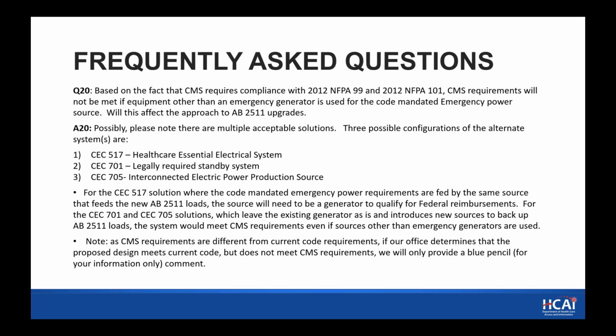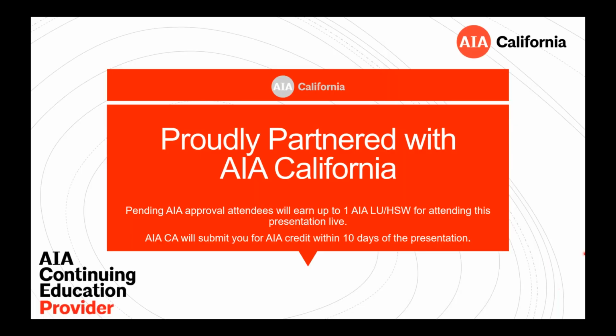Just a note: for all the plans we look at, if there's a code violation, we'll write that as a comment that needs to be cleared. If it's code compliant but doesn't meet CMS, we'll put a for your information only, or blue pencil, comment that just alerts you that while the system is code compliant, the facility might not qualify for CMS reimbursements. And that is the last of the frequently asked questions.